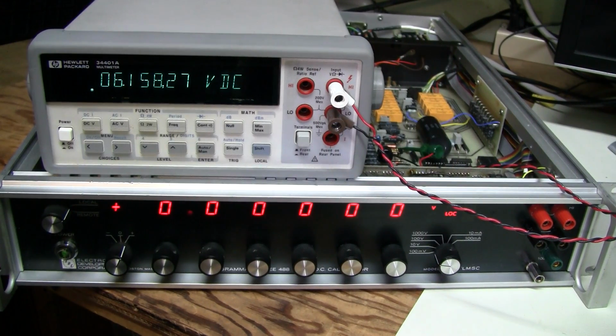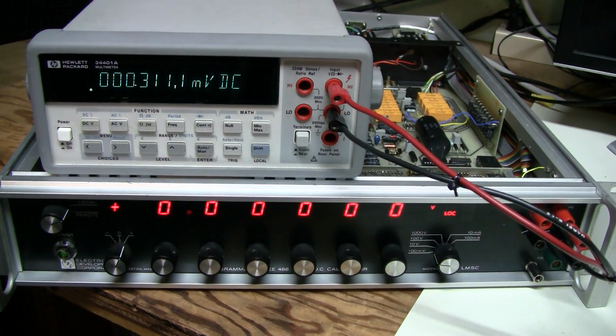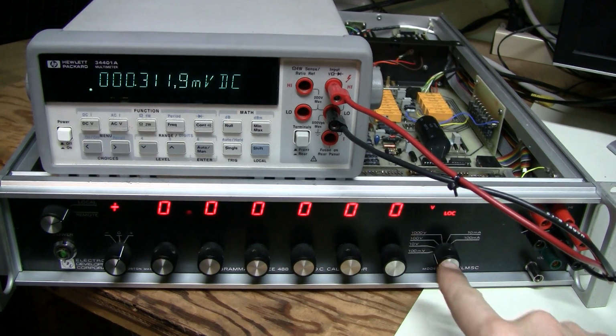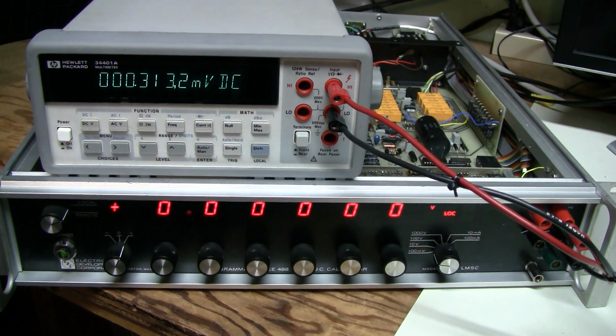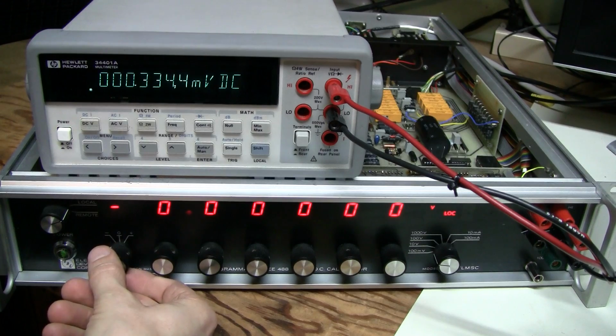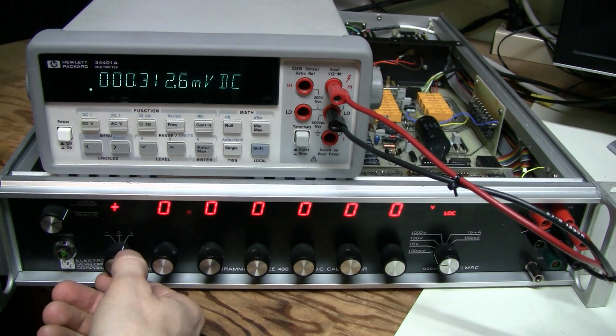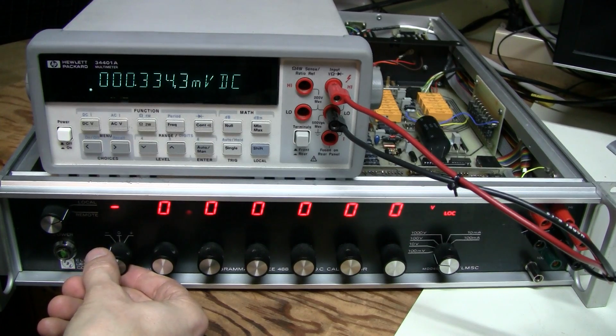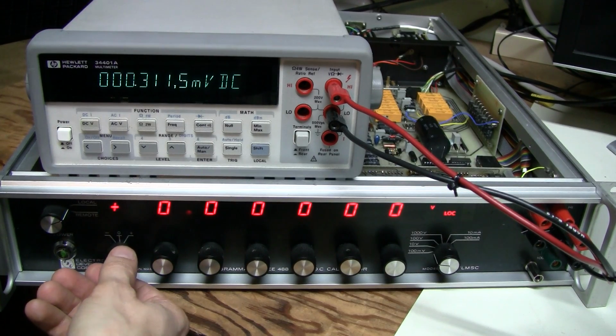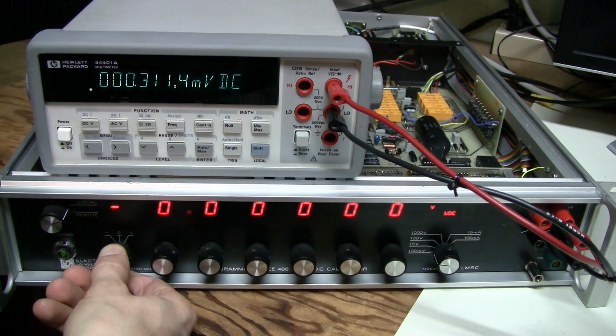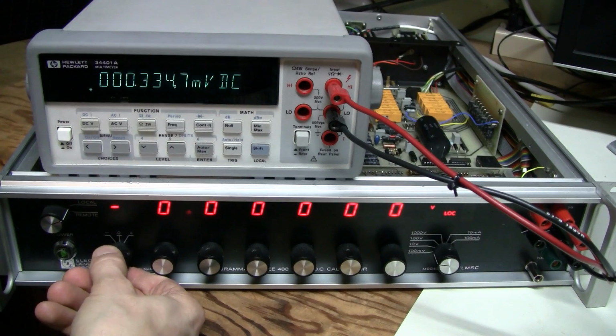The first step in the calibration procedure is to set the zener diode voltage to the voltage on the tag, which should be 6.1588. There we go, done that. The next step is to adjust the 0 point of the amplifier, as we've seen before. So we need to set in the 10 volt range 0 setting and switch the polarity back and forth and adjust the potentiometer so that we have the same magnitude but the opposite polarity, which is not the case right now. We have about the same magnitude, not quite, but the same polarity.